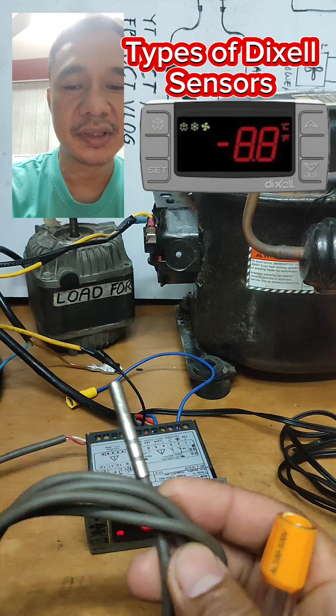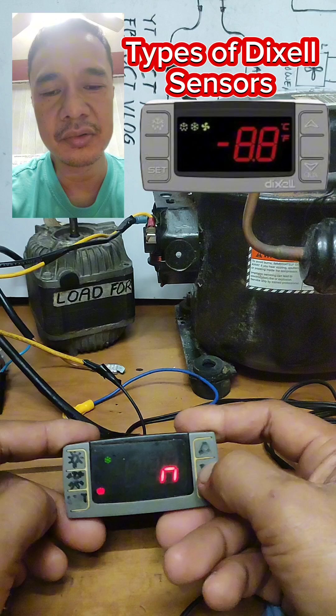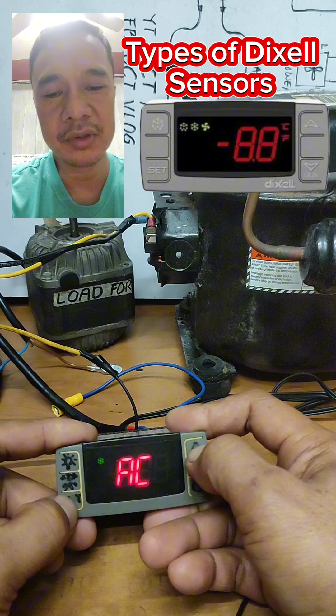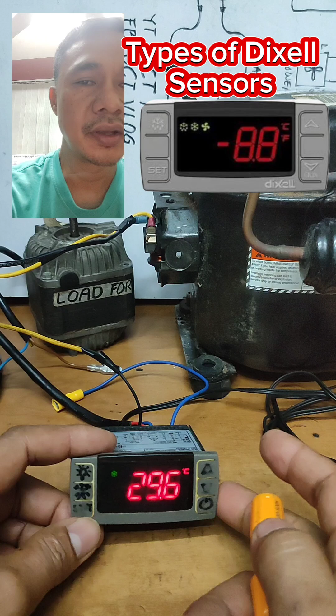Now let's see what happens again. I'm going to disable the P2. Okay, accessible, preset, and I'm going to choose no. So now my sensor is only one, the evaporator sensor is disabled, and look, we don't have an error now.